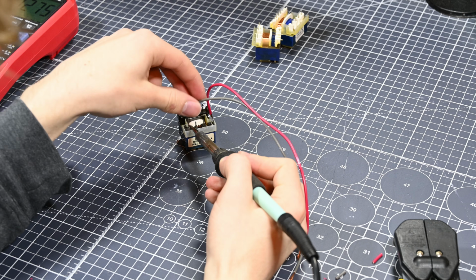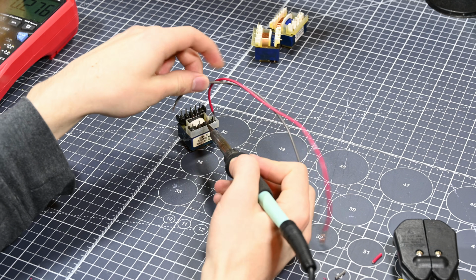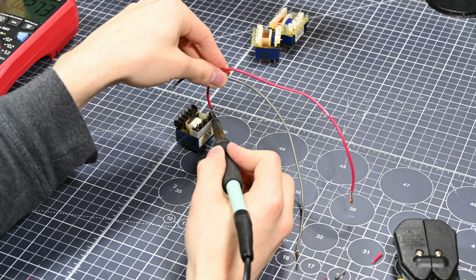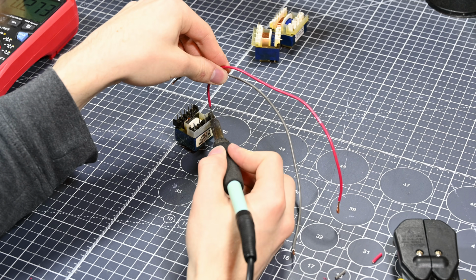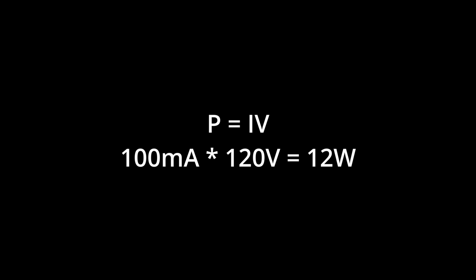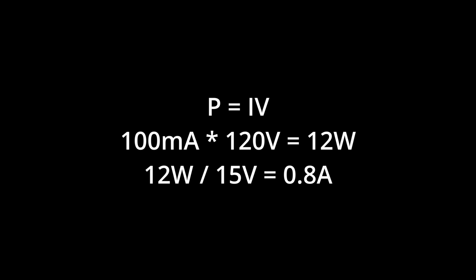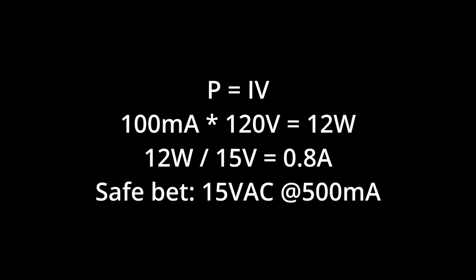Figuring out how much current these can provide is a little trickier. However, one of the transformers had its primary fused at 100 milliamps on its PCB, which translates to about 12 watts on the primary, and at 15 volts on the secondary, that's about 0.8 amps. Being conservative and accounting for some losses, I believe these transformers are good for 15 volts AC at roughly half an amp.